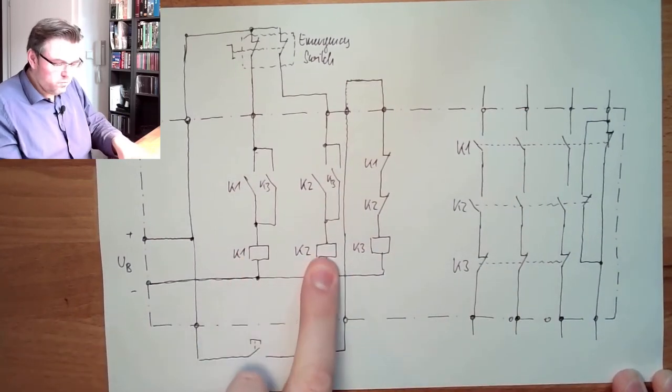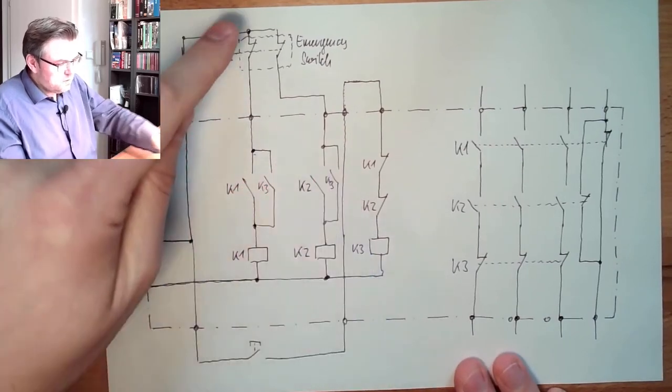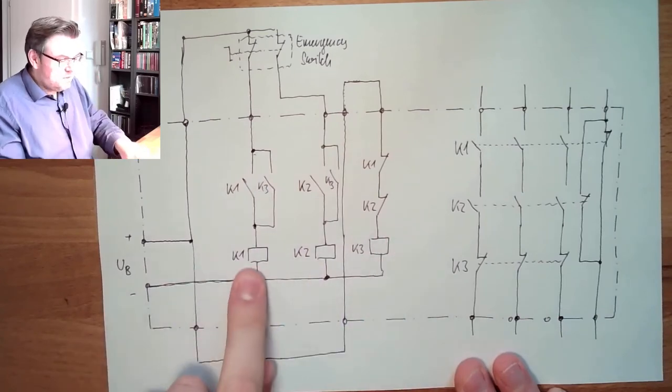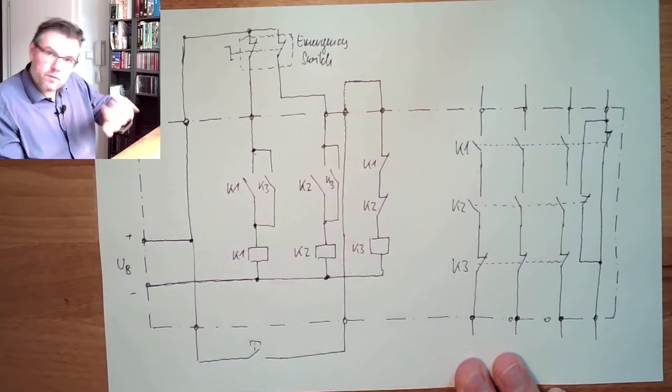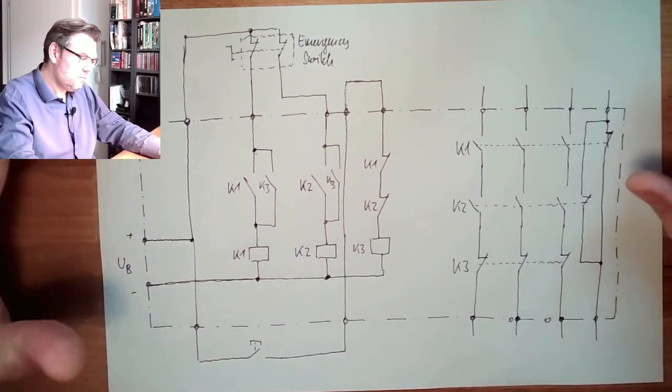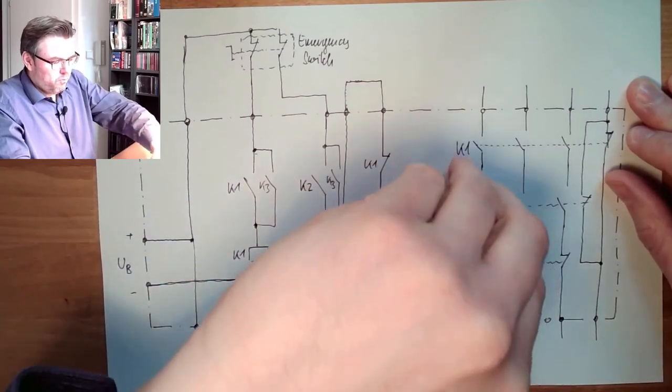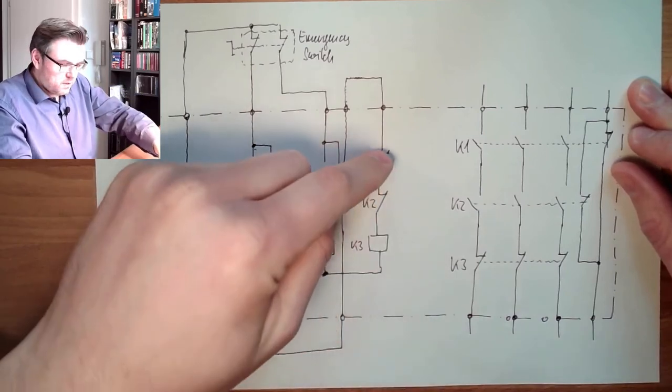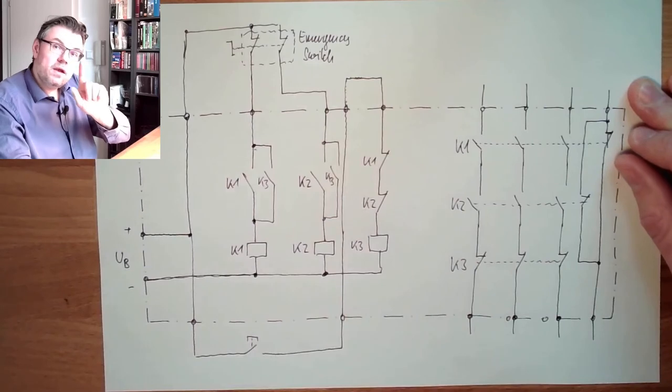So K1 is energized, K2 is energized, and K3 is off. K1 is closed, K2 is closed, and K3 is off. K3 is off is simple, because if K1 or K2 is closed, this will be open and K3 is off anyway. And this is why those two things are inside there.